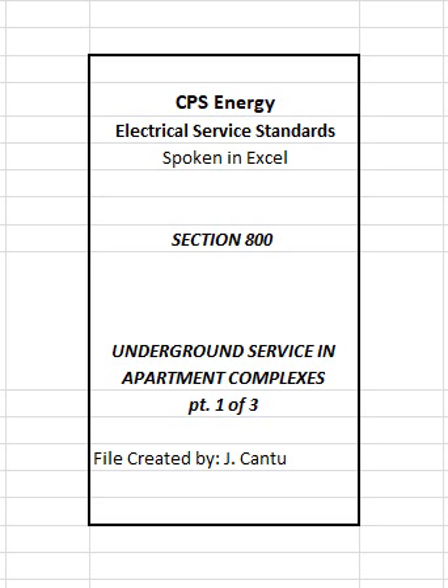3. All transformer pads must have a minimum of 3 feet of clearance around the sides and rear of the pad and 6 feet of clearance in front. The front side of a transformer pad is defined as the side where the transformer door/opening is located. 803 2 CPS Energy Job Sketch. Customer shall stake transformer locations using the information in the CPS Energy provided job sketch.